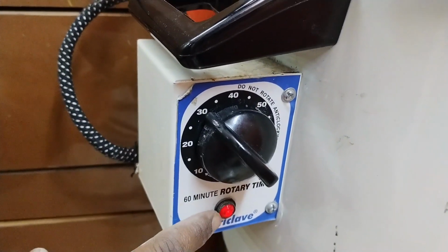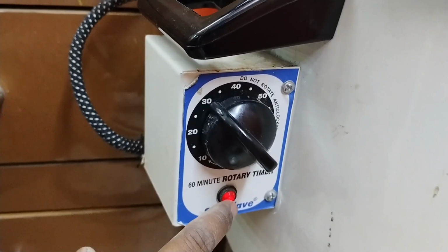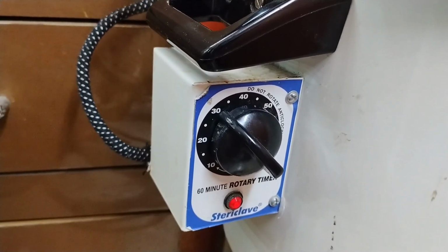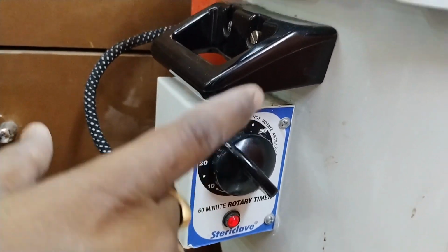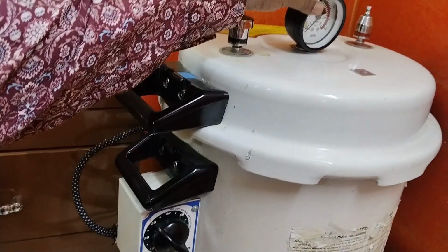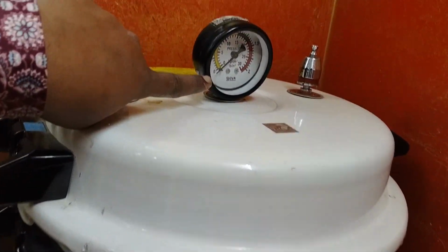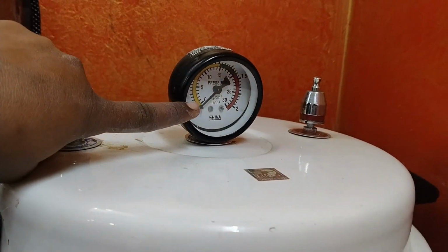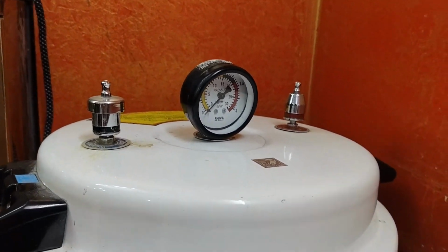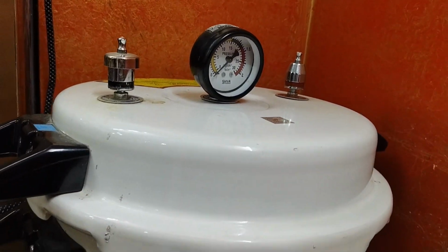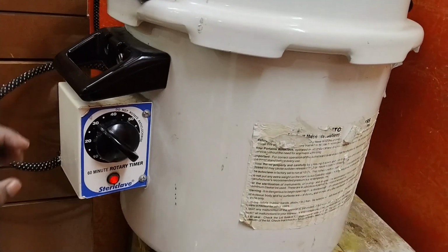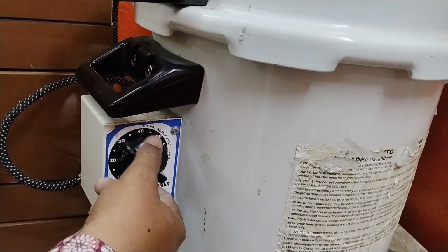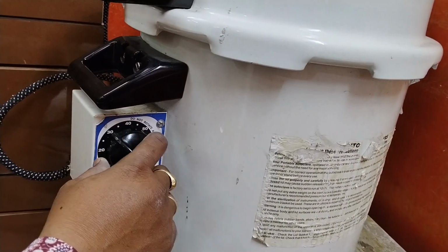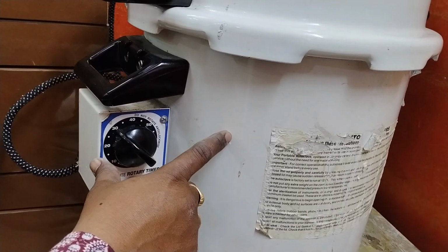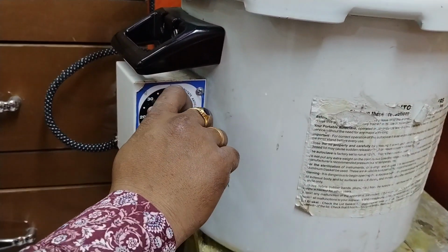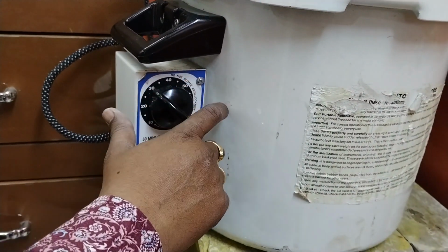The red button is visible, the bulb is on. We should wait for 30 minutes to complete the autoclave. Now the pressure is 0. It will rise after heating the water inside it. You should not rotate the timer anti-clockwise, the springs will be damaged and it will lead to failure of the autoclave. If you go for 40 minutes also, you should leave it like that.